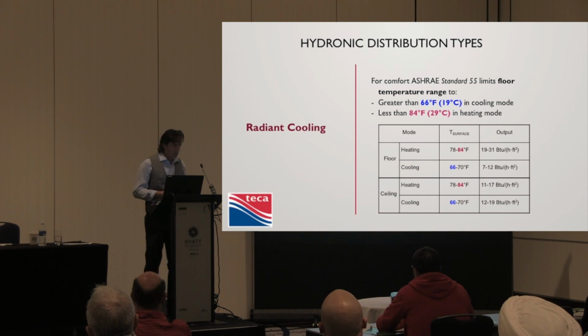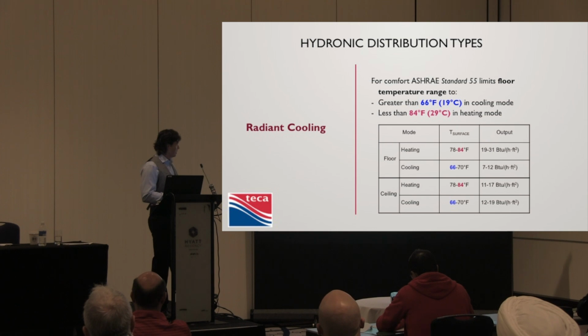So one of the limitations, again, we go back to ASHRAE 55, limits the temperature range. It's got to be greater than 66. That's your floor surface temperature, and of course less than 84. We already talked about this one, but this is the other one. So no less than 66. So that's our bottom line. So how much cooling can we actually do with a surface temperature of 66? Well, let's look at it.